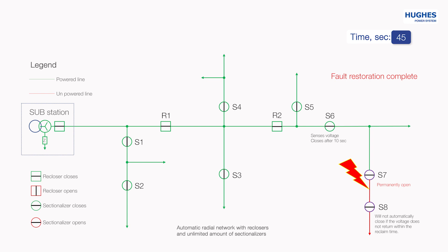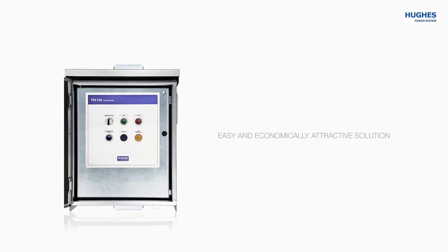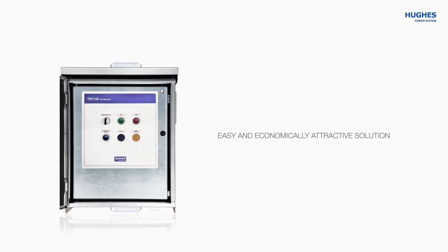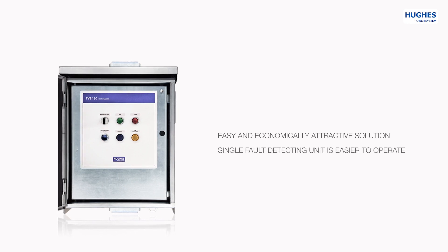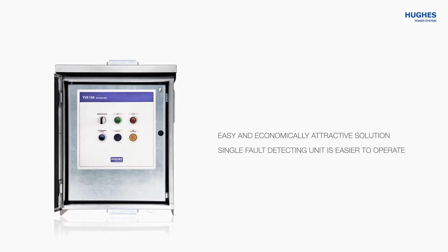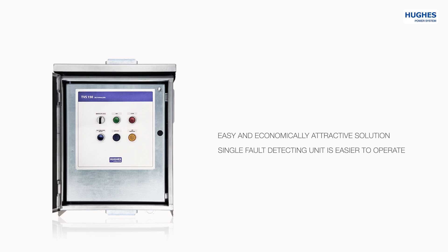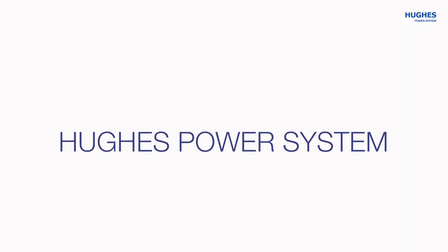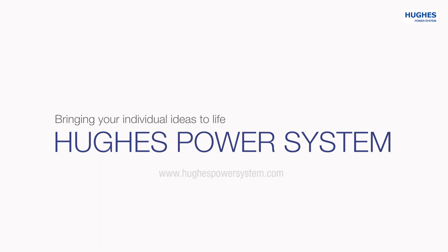S7 is now permanently open. S8 will not automatically close if the voltage does not return within the reclaim time. To summarize: AutoSelf is an easy and economically attractive solution to divide the line into small sections by using existing disconnectors or load-break switches. All faults are detected by a single fault detection unit like a substation protection relay or a recloser. Operating one advanced fault detection unit is far better and safer than multiple units from different brands with different functionality. By designing and producing our own parts and components, we bring your individual ideas to life.